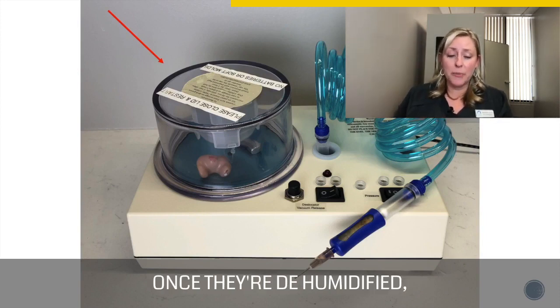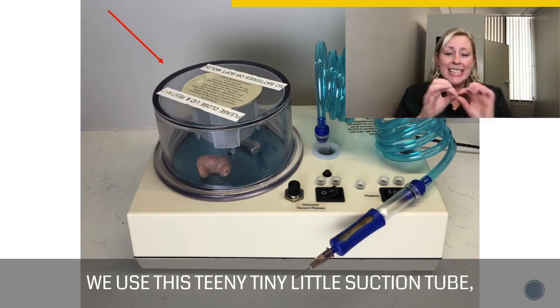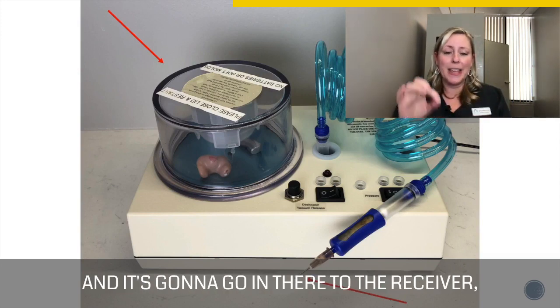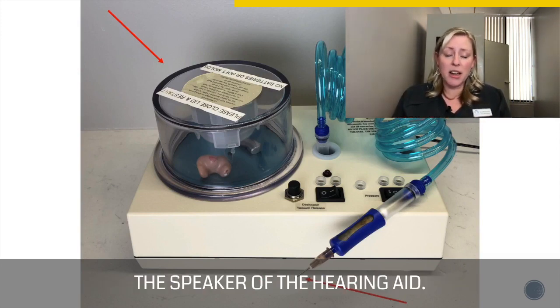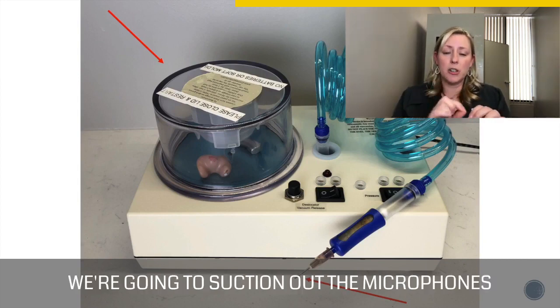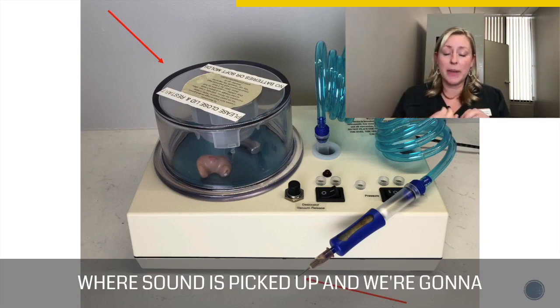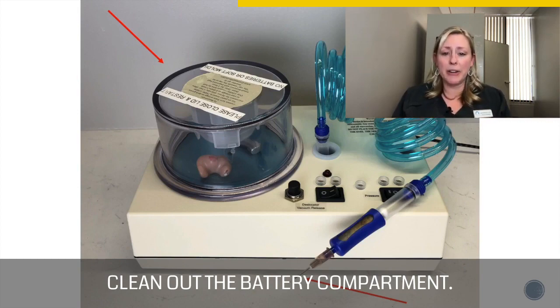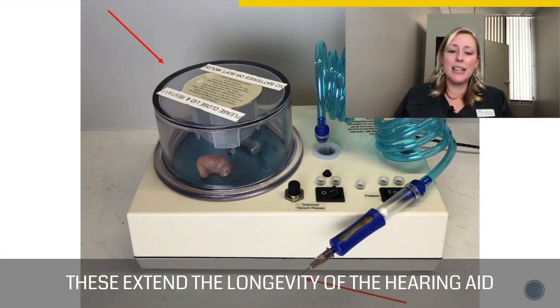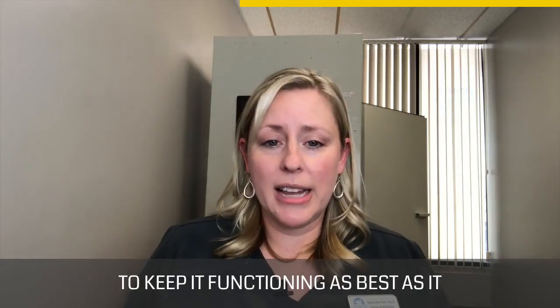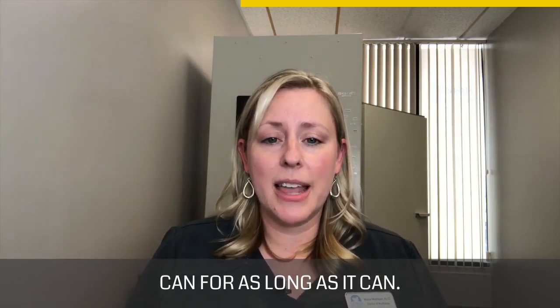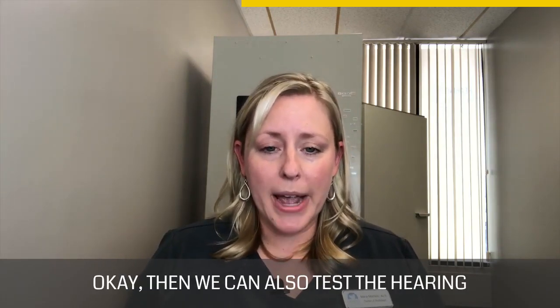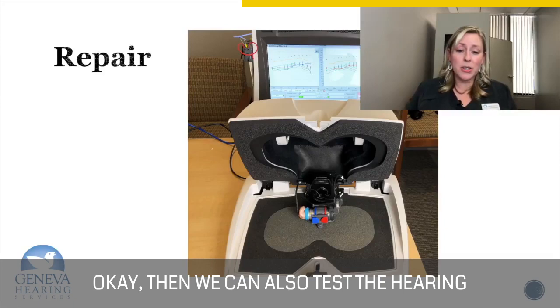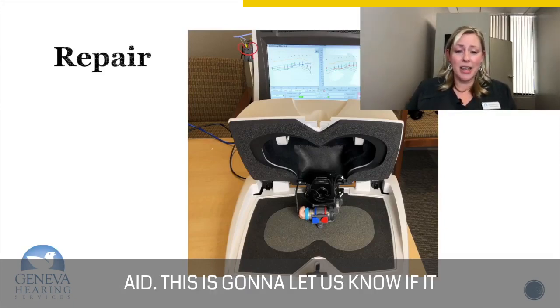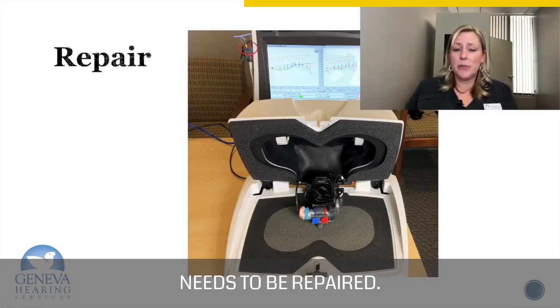Now, once they're dehumidified, we use this teeny tiny little suction tube, and it's going to go in there to the receiver, the speaker of the hearing aid. We're going to suction out the microphones where sound is picked up, and we're going to clean out the battery compartment. And again, this helps the longevity of the hearing aid, to keep it functioning as best as it can for as long as it can, okay? Then we can also test the hearing aid. This is going to let us know if it needs to be repaired.